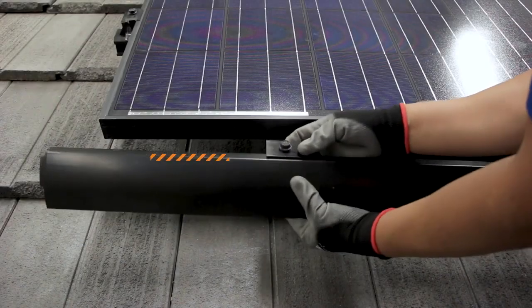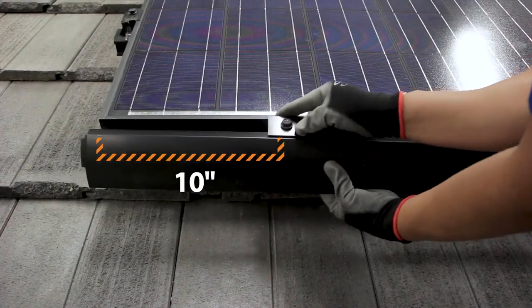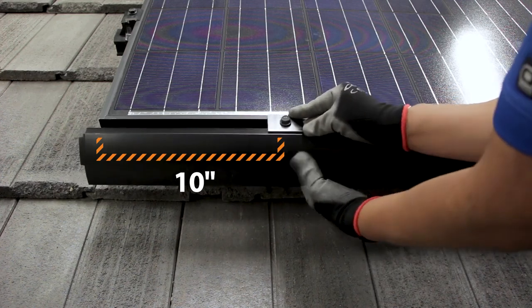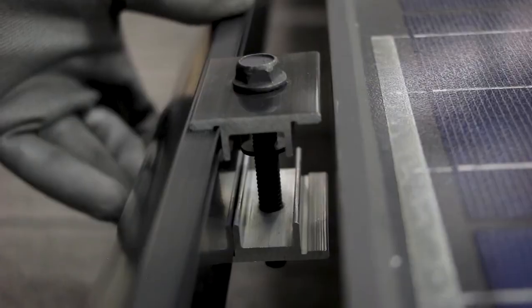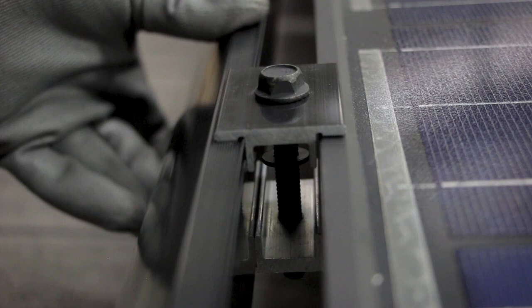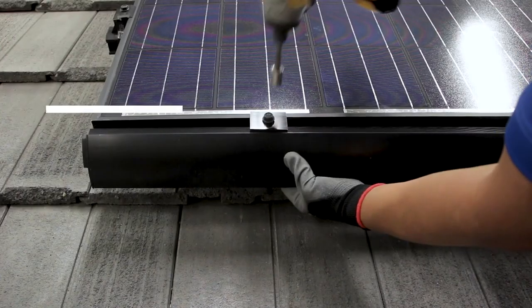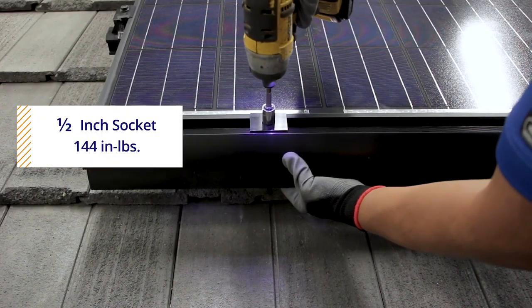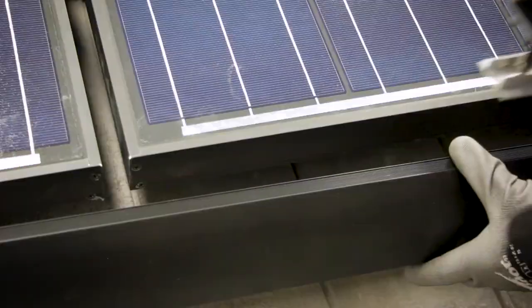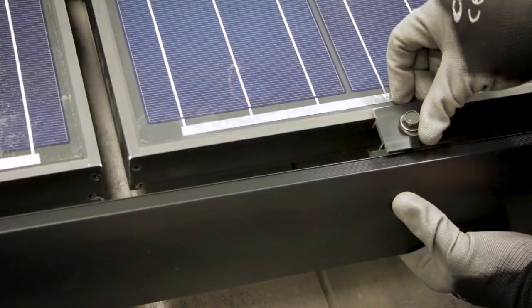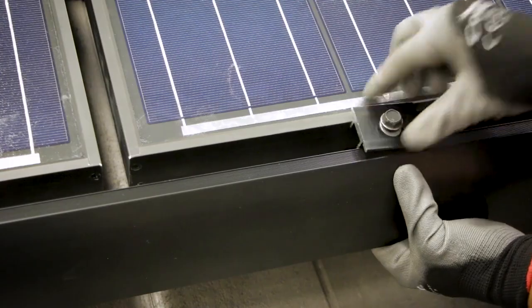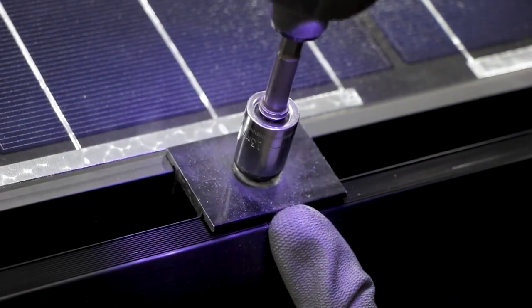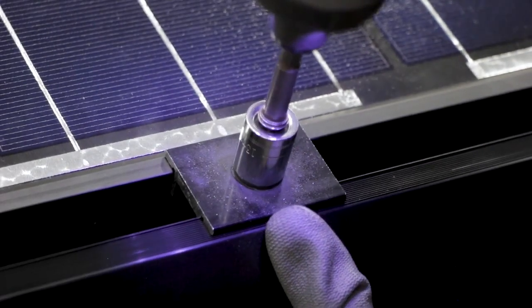Locate the first clamp in the row no more than 10 inches in from the edge of the module. Ensure that the flat faces of the clamp are parallel and fully engaged with each other, and then tighten the skirt clamp to 144 inch-pounds using a half-inch socket. Now, working your way down the skirt, drop the next clamp in roughly the same location on the module relative to the clamp on the last module, and then tighten it down.